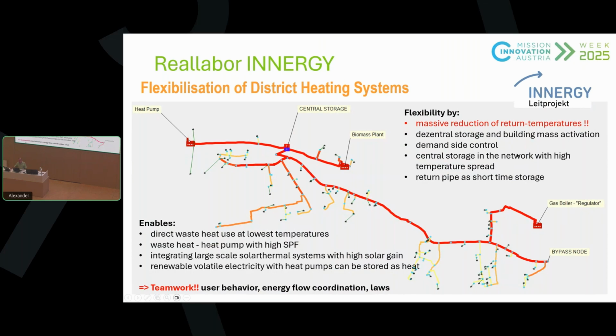So demand side control, as I said, is something important. It's not always necessary to heat exactly at the same time because it's cold outside. It can be shifted some hours earlier, some hours later. Central storage is the same as the decentralized storages, and also the network itself can be used, so especially the return pipe as a short time storage. If this is really low temperature we get into the network, then this can be used more and more also as a short time storage.